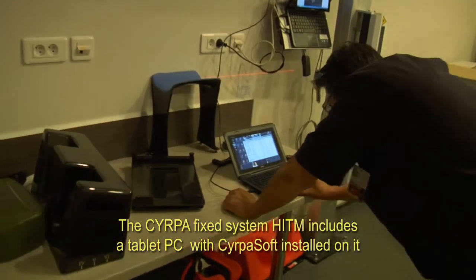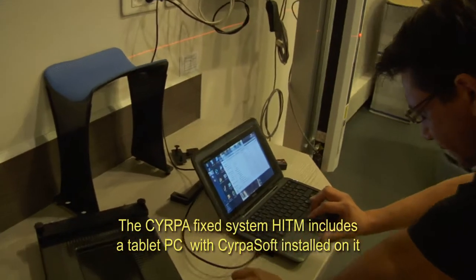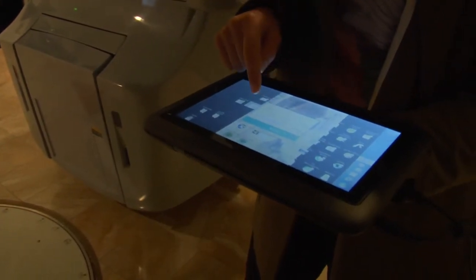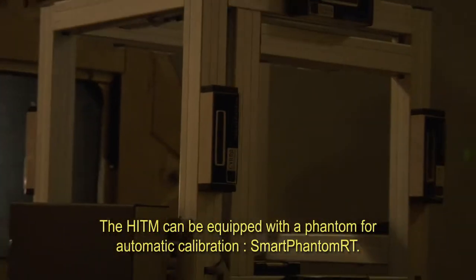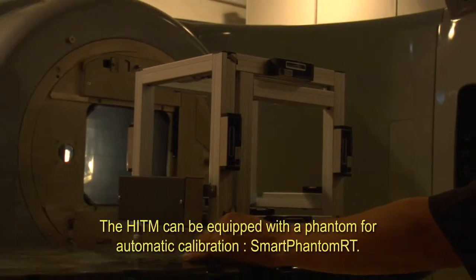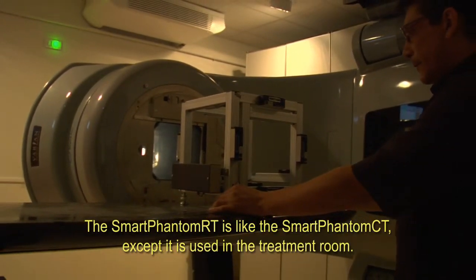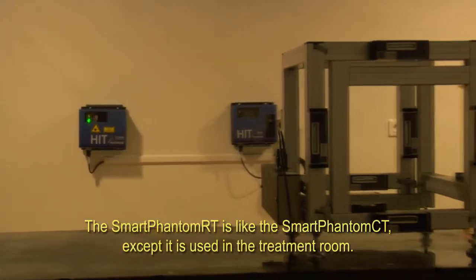The CYRPA fixed system HITM includes a tablet PC with CyrpaSoft installed. The tablet communicates with the lasers through a wireless connection. The HITM can be equipped with the Smart Phantom RT for automatic calibration. The Smart Phantom RT is like the Smart Phantom CT, except it is used in the treatment room.